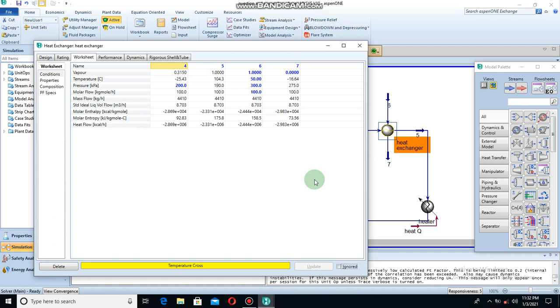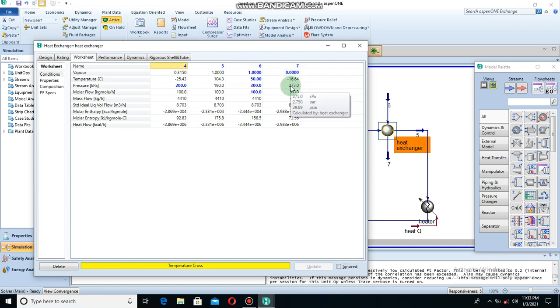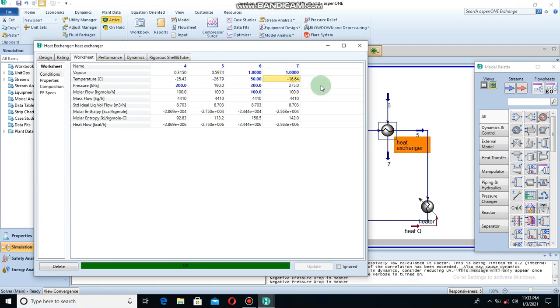I was going to show you how to get that done. One technique is to manipulate the phase. Right here we have propane in vapor form at the hot stream, and when it was exiting the heat exchanger it came out as a liquid phase. By keeping it in the same phase — wow, it converged to a minimum approach temperature. So definitely the phase was one of the reasons for the temperature cross.